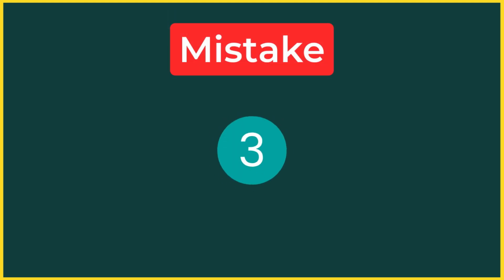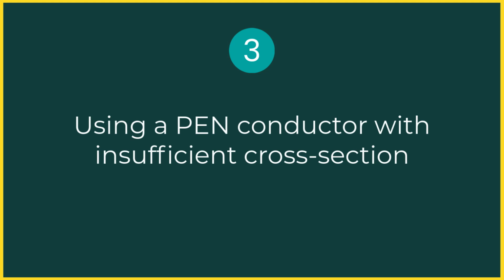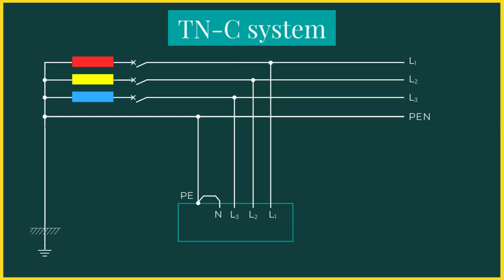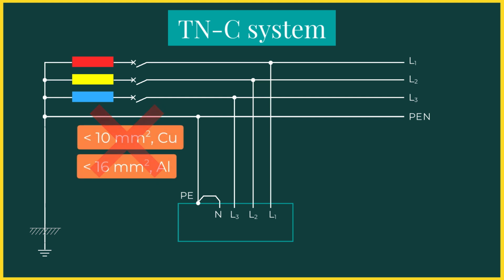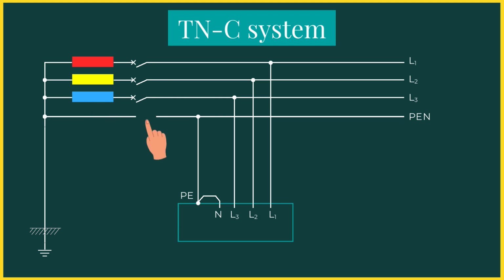Mistake 3. Using a PEN conductor with insufficient cross-section. Standards do not permit the use of a PEN conductor with a cross-section less than 10 mm² copper or 16 mm² aluminium. Below these values, the conductor is more likely to break under mechanical stress. Such a failure can result in the loss of the protective function and create a serious risk of electric shock.